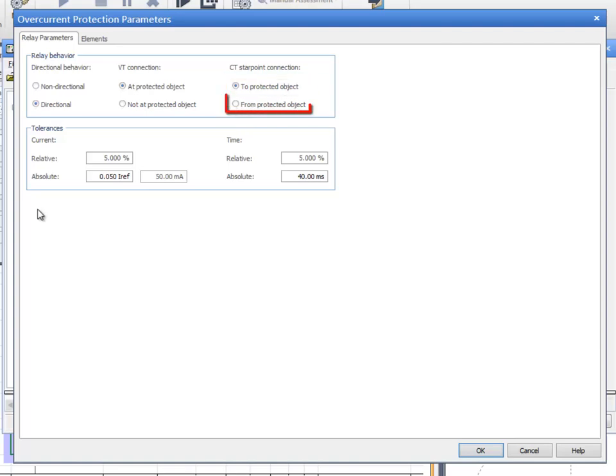Select From Protected Object when the CT start point is connected in the bus bar side. In this case, the currents generated by the CMC have a 180 degree phase shift compared to the currents that the primary network would have.